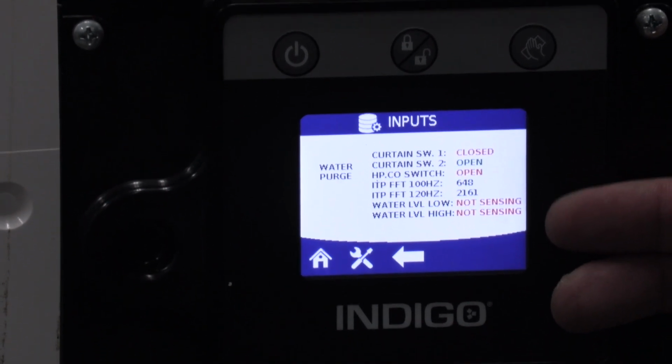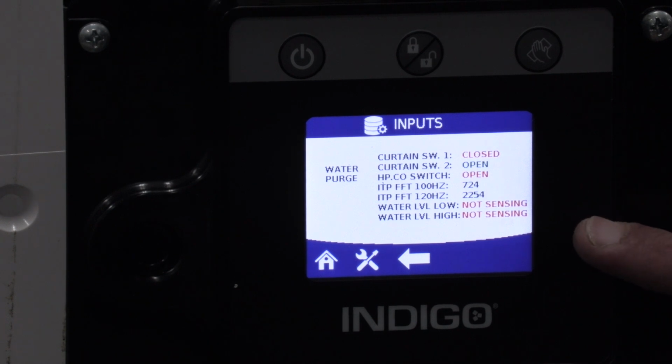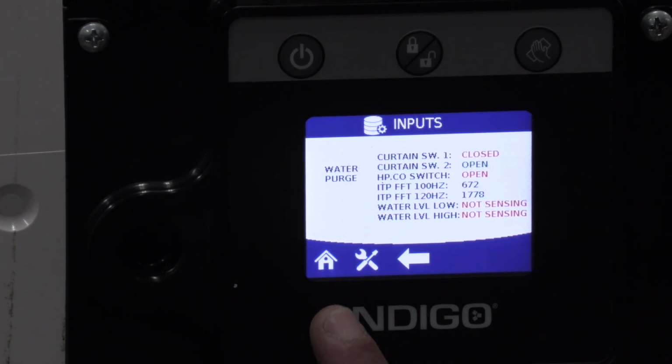We are in our timed water purge. It's 45 seconds. You've got the dump valve and the pump trying to drain out old water, and then the refrigeration starts up. So what we're waiting for is pre-chill when we're supposed to get water. And our probe tells us we don't have water. So come pre-chill, we should get some. All right, there's the compressor. Any second now, this is going to go from water purge to pre-chill.